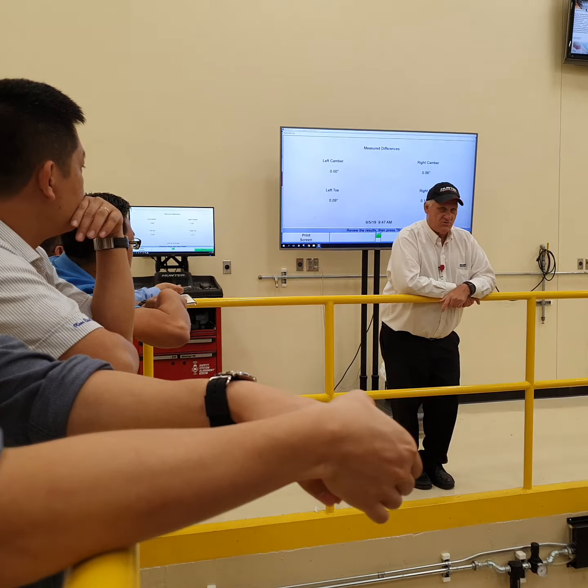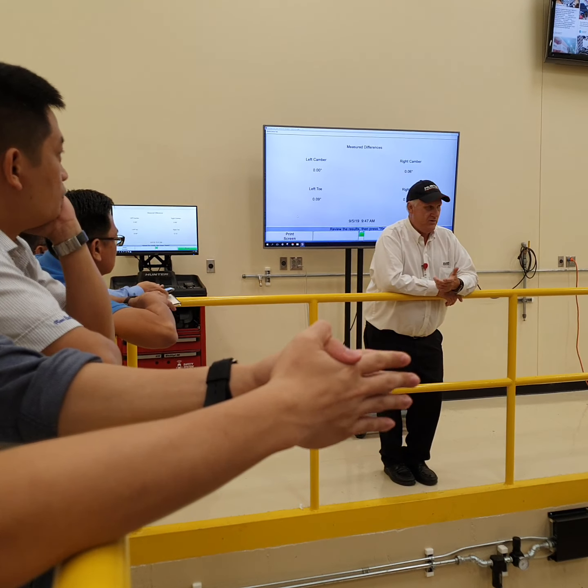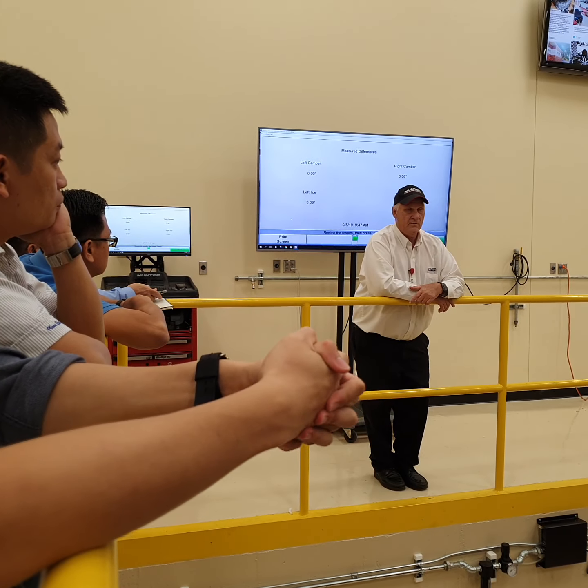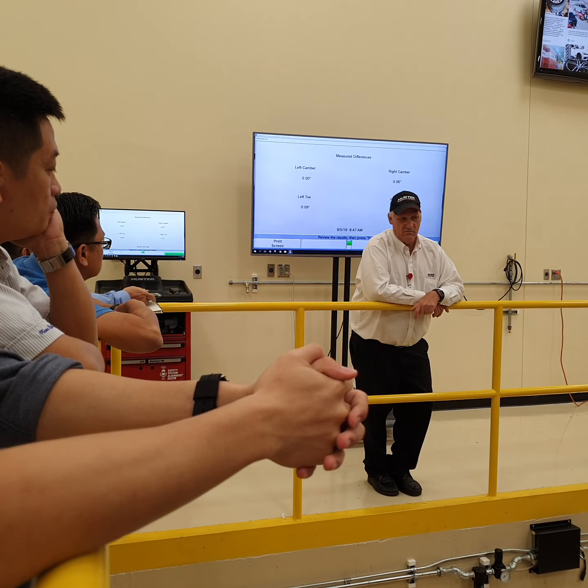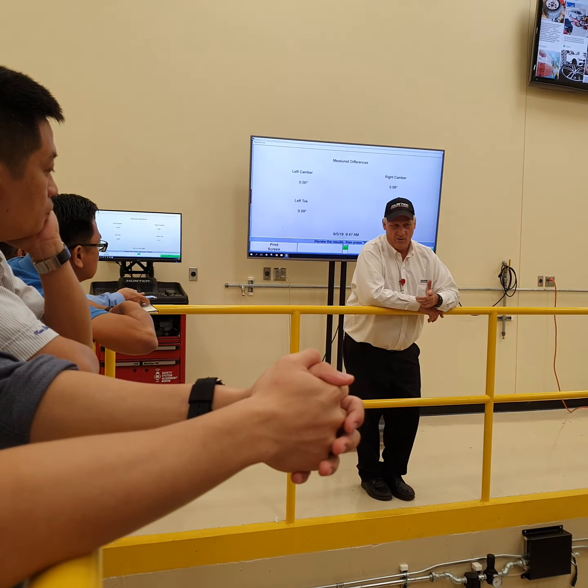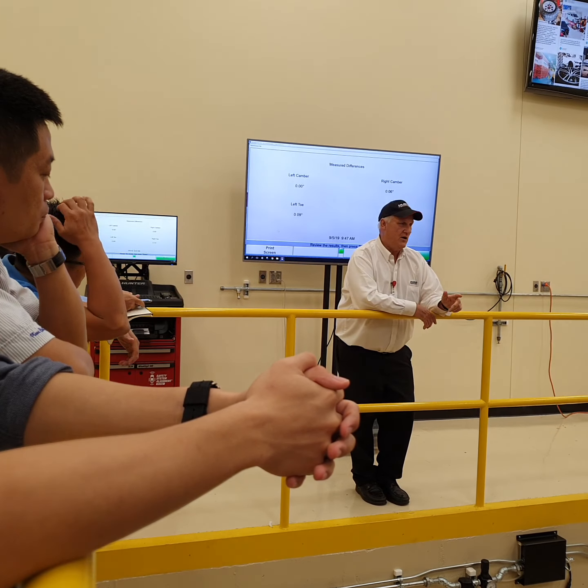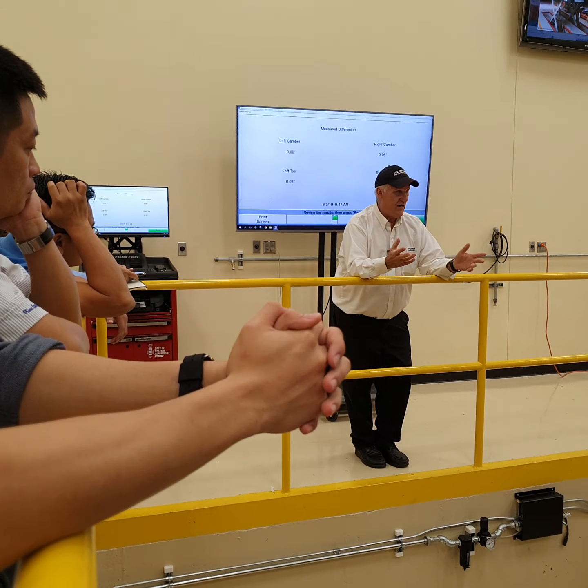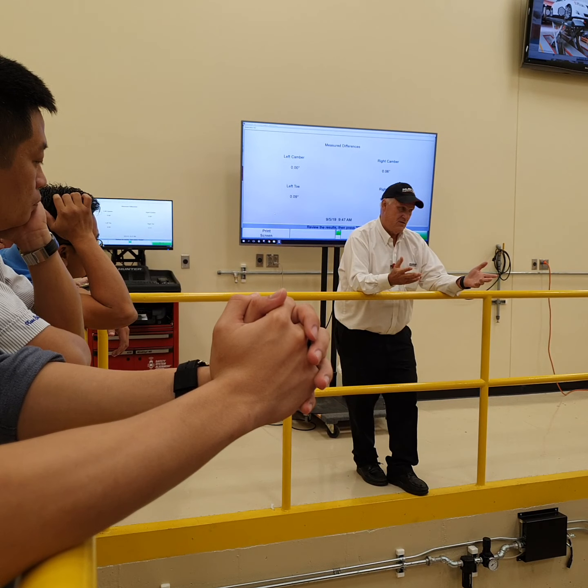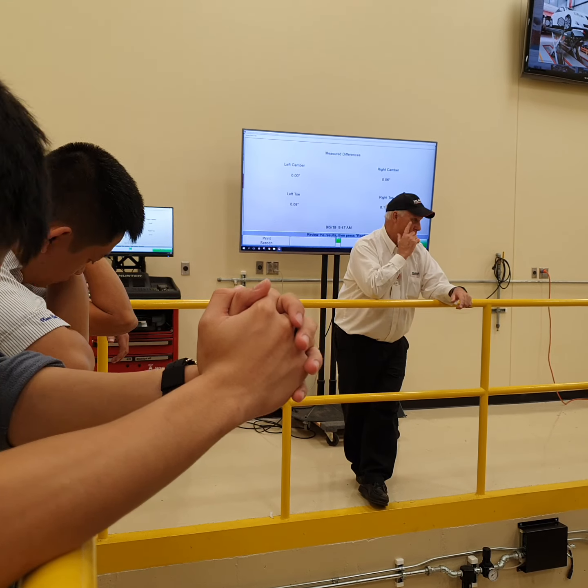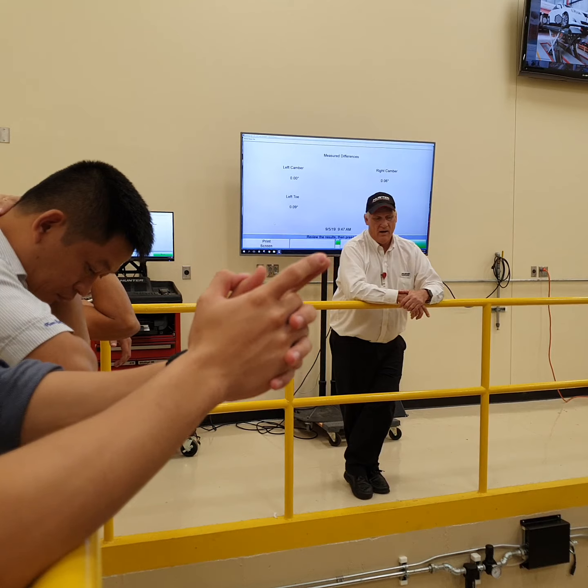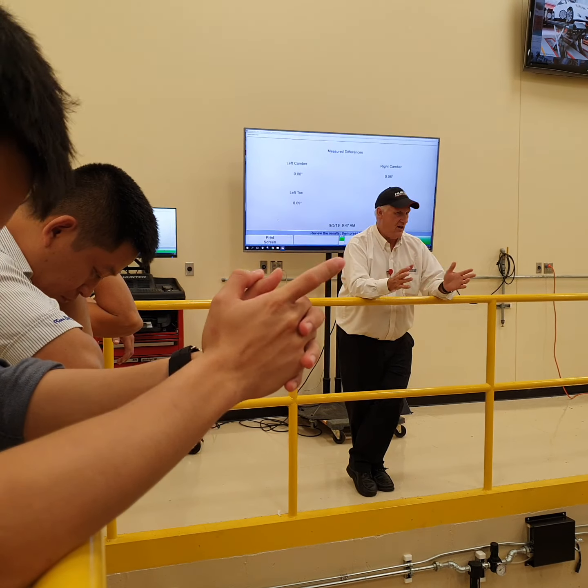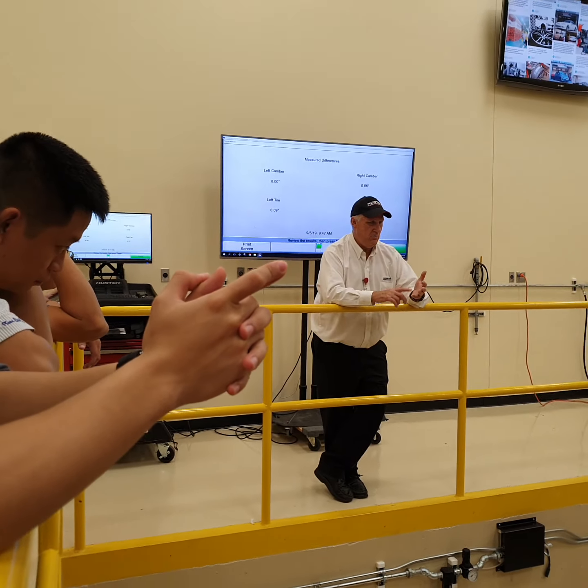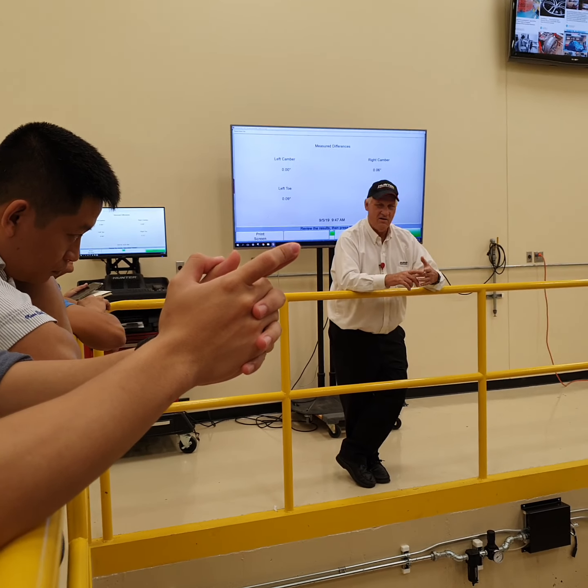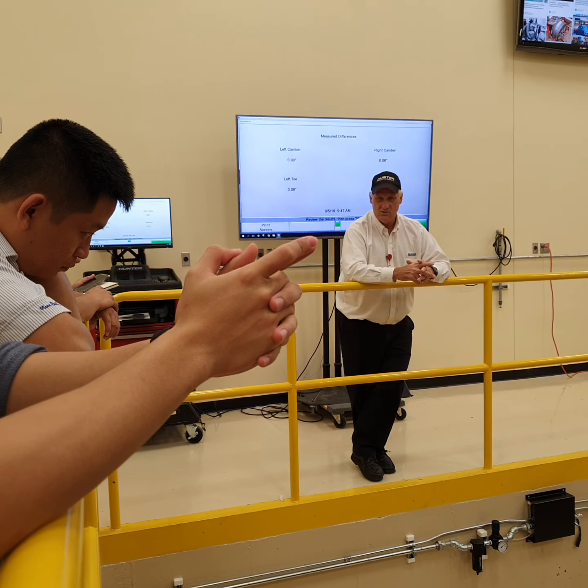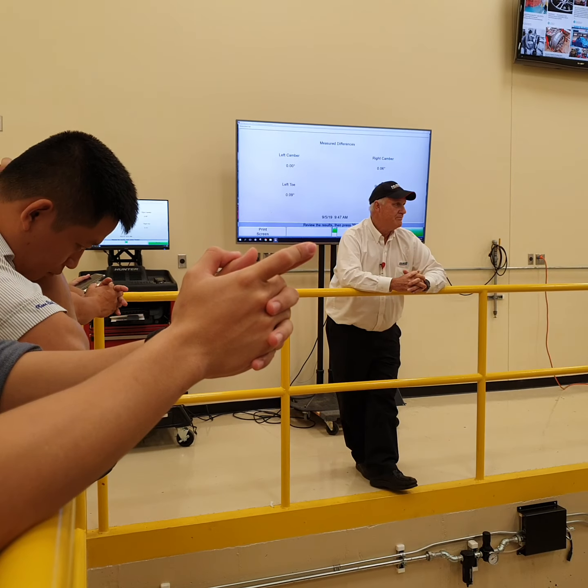So that's reverse sensor test. That's something the customer can do. It's something that the customer should be trained to do. He should understand why he's doing it. I don't think the test is difficult. It can be done with 4 sensors, 760s. If he's got 500s, he can do it. So your customers that have older equipment can do it too. It's an electronic device, subject to humidity and temperature changes, and it wouldn't be a bad idea to do this check once a week, right?